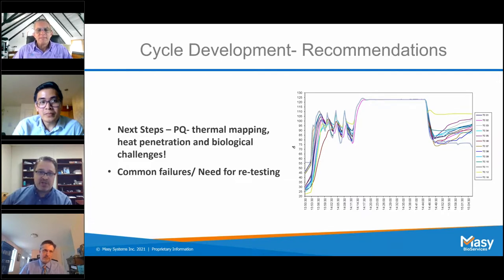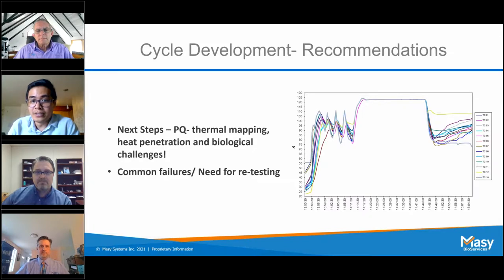Containers as well, placed upright inside the chamber during sterilization. Surprisingly, if you don't get that evacuation and that steam to replace the air inside that container, you'll have issues there as well. Yeah, orientation is key. Tuan or John, do you want to add to that? Yeah, just to add to Sylvan's point, you want to look into the load item orientation as well. If you have items stacked on top of each other, it may make it even harder for steam to seep through to whatever items you need to get sterilized. So that's another point to look into.